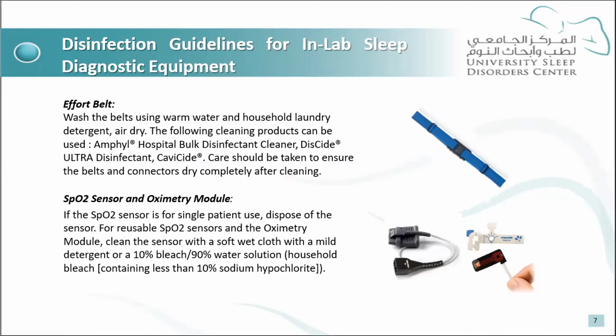Next is the SpO2 sensor. As you are all aware, SpO2 sensors or probes come in two options. The first one comes as disposable, so you can use it for the patient, then dispose of it. The other option is the reusable. When we talk about the reusable, you need to use a special disinfectant procedure: you need to get a cloth and immerse it in a mild disinfectant, or in 10% bleach with 90% water. So 10% bleach and 90% water. You immerse the cloth in this solution, then clean the SpO2 sensor, make sure that it's dry, then use it for the next patient. Okay, so this is a very important procedure to be implemented.